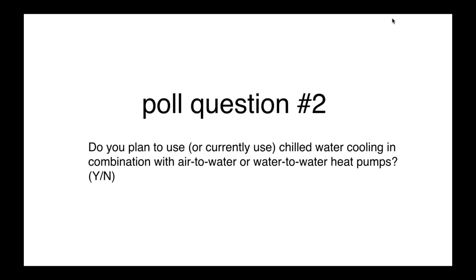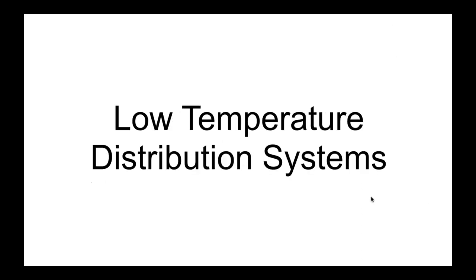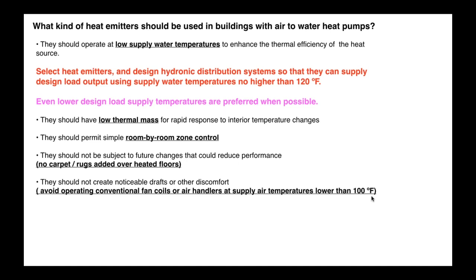So let me just move this control panel here, and then we're going to go back. So let's talk about low temperature distribution systems. We are going to jump into cooling here, but when you're dealing with heat pumps, and again, this applies to geo water to water as well as air to water, the lower the supply temperature, the better. I often suggest nothing higher than 120 degree water at design load. It's not a standard. You won't find it in an ASHRAE handbook, but it is a practical number.